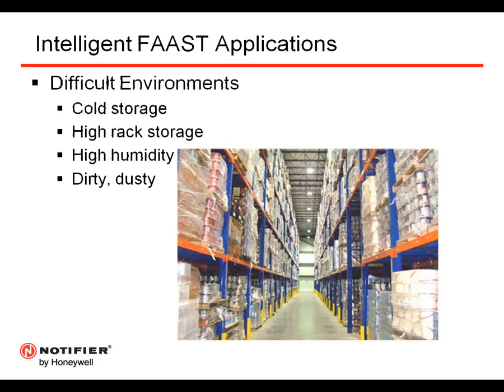Also, difficult environments, and there's a number of difficult environments where Intelligent FAAST could be applied. Start off with cold storage. You have the cold storage area. The environmental parameters within that cold storage area might not meet the listed operating parameters for a spot-type detector. A spot-type detector is typically rated or listed to be installed in an application from 32 to 120 degrees. So if you're talking cold storage where it's below 32 degrees, they can install an Intelligent FAAST unit and locate it outside of that cold storage area, or outside of the parameters that is below that temperature, and then run the pipe network from the Intelligent FAAST unit into the space.